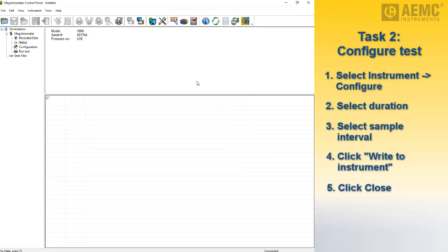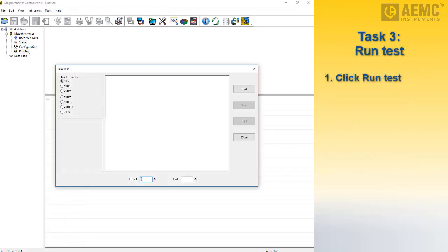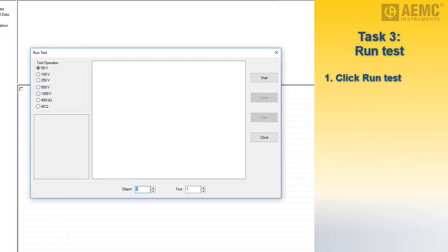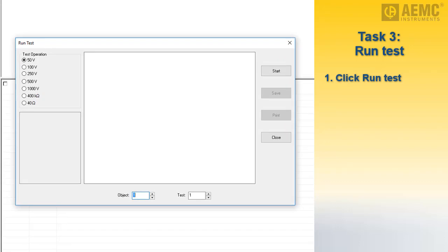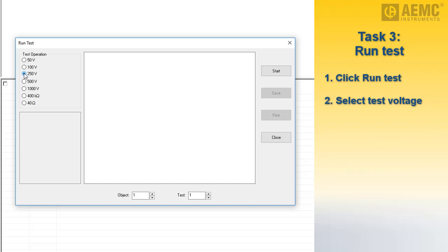With the test setup complete, we can now start the test. Click Run Test in the navigation frame to display the Run Test dialog box. On the left side is a list of available test voltages from which you can select. Note that these will override the voltage selection indicated by the instrument's dial. For our test, we will select 250 volts.